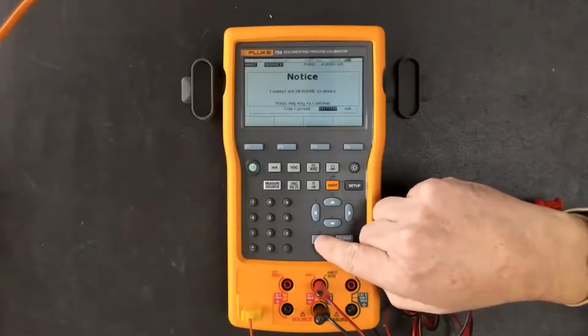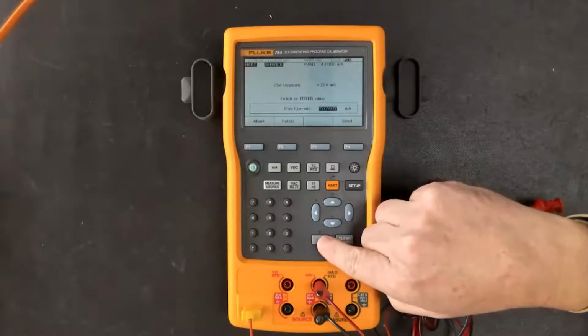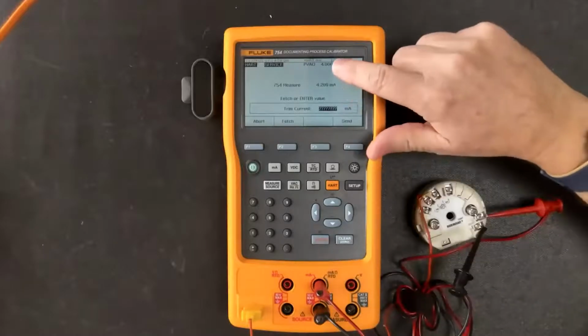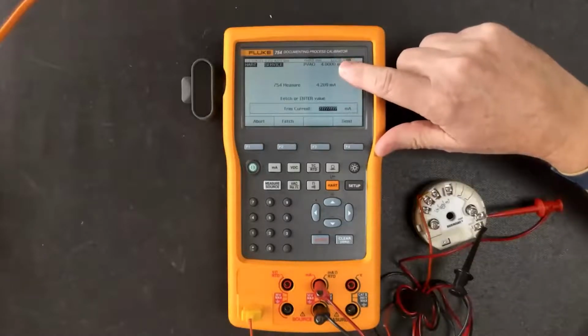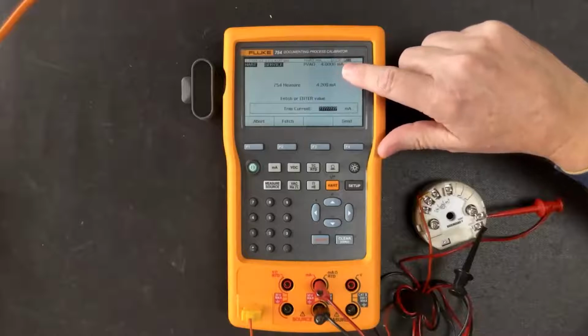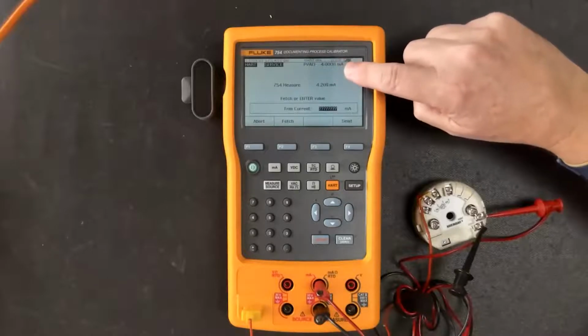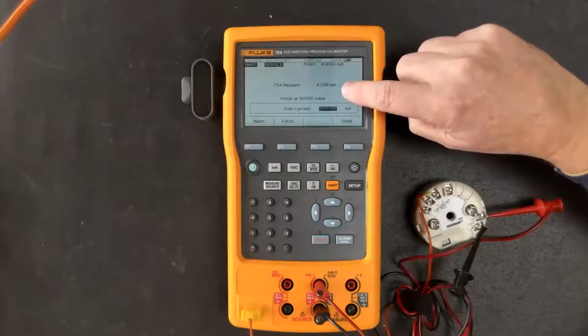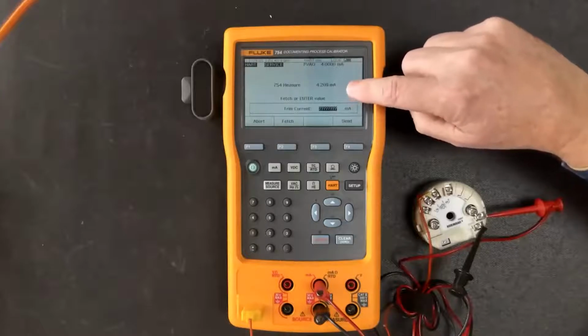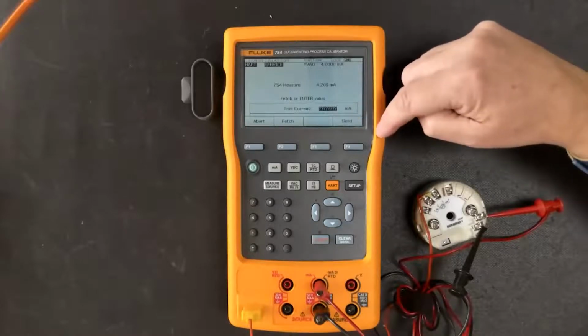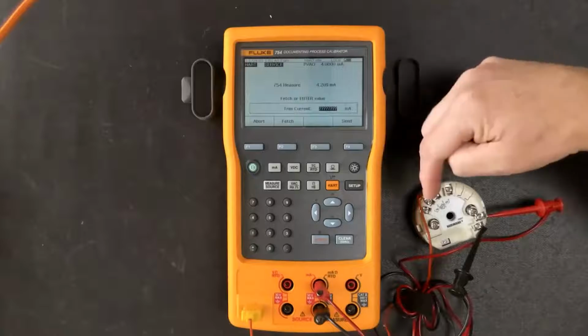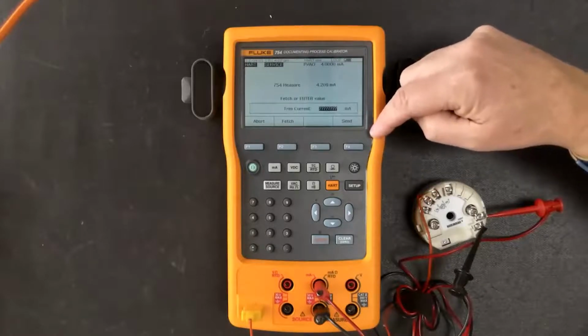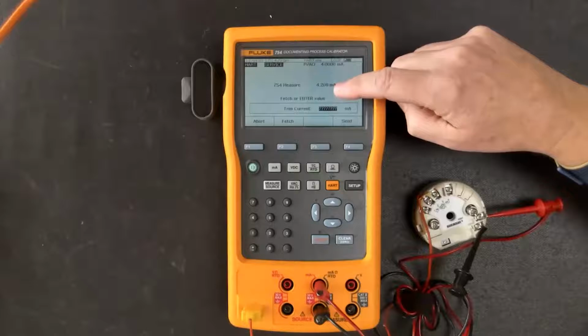Make sure we're connected to the device. Okay. Now if you'll notice the PVAO, this is a process variable analog output of the transmitter. The transmitter thinks it's putting out 4 milliamps, but the 754 says, well, no, I'm reading 4.2. And of course, the calibrator is going to be at least 4 times as accurate as the device it's testing. So this is the number that we're going to go with.